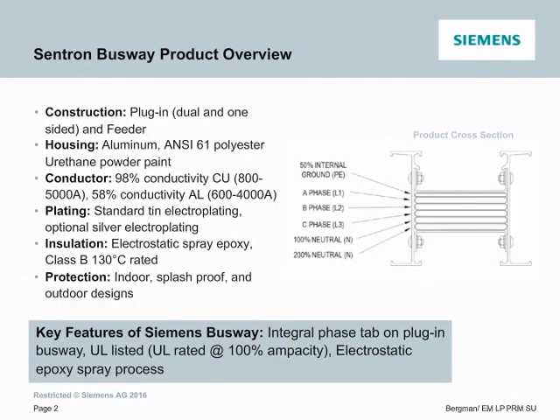On this slide, I really want to drive home a few key features of the Siemens Busway system. One of them being the integral phase tab on plug-in busway. Integral phase tab means no welds in your conductor. The integral phase tab is important as it makes sure that we have a mechanically strong and electrically effective connection point to bus plugs. The second key feature of the Siemens Busway system is the electrostatic epoxy spray process.